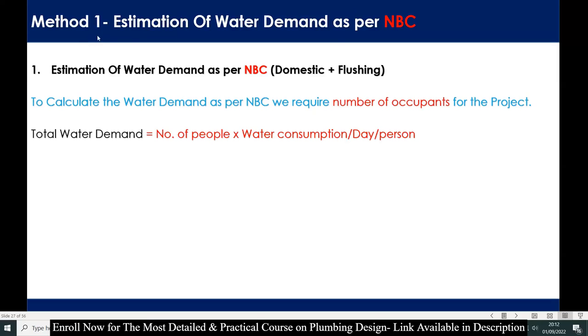As per Method 1, that is as per NBC, what do we exactly need? If you are going with the NBC standard, you need the number of occupants inside the building — this is the only thing required to calculate the demand. The formula is: total water demand equals number of people multiplied by water consumption per day per person.